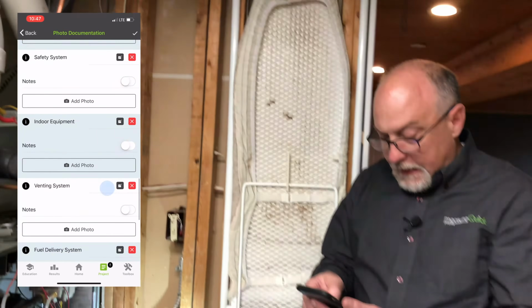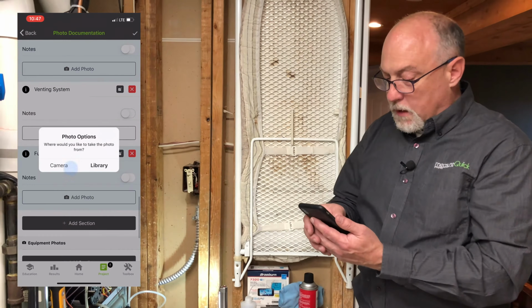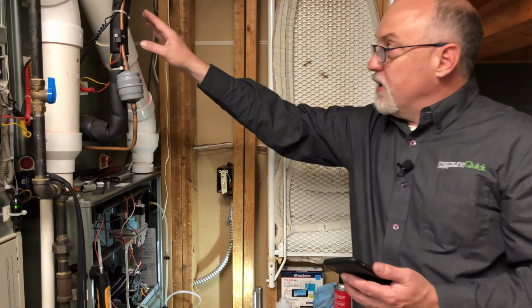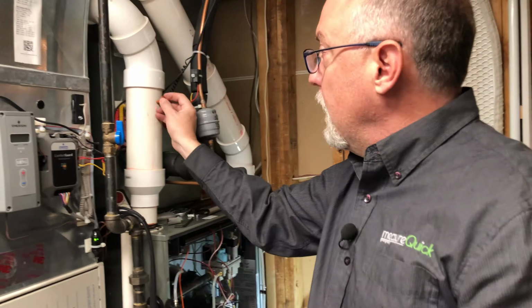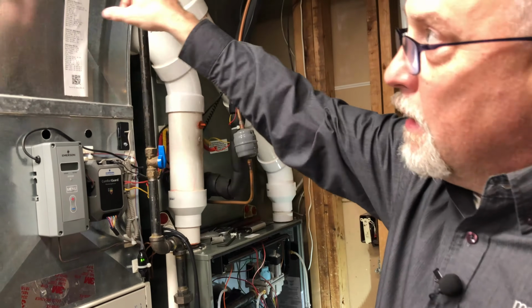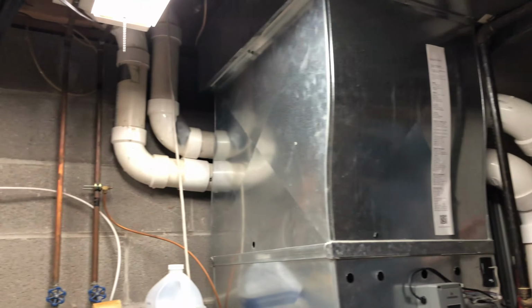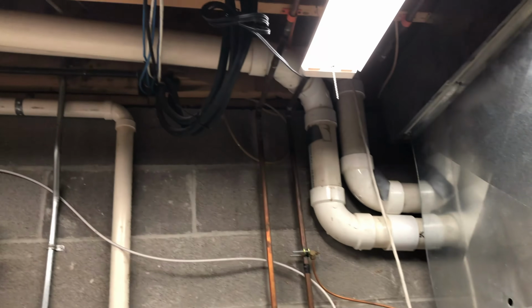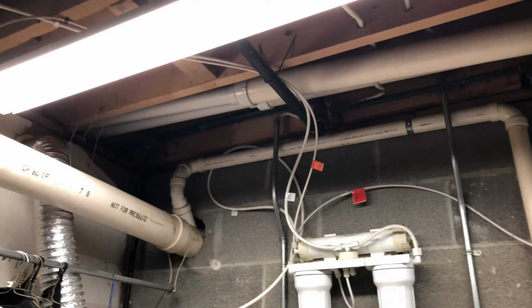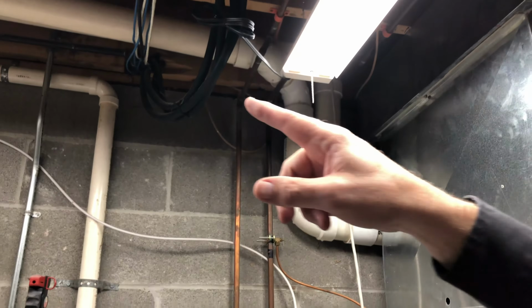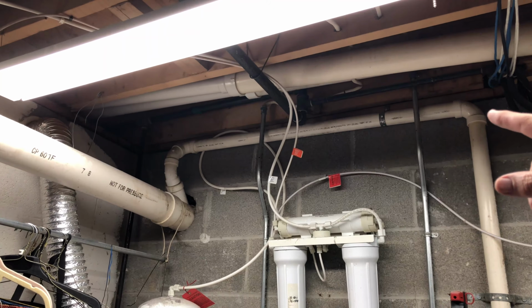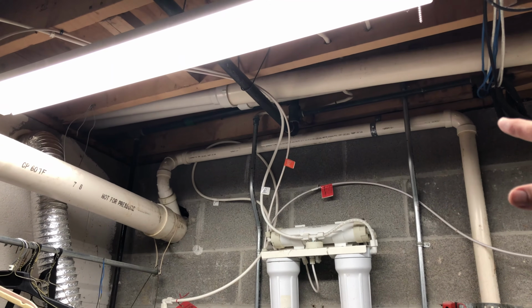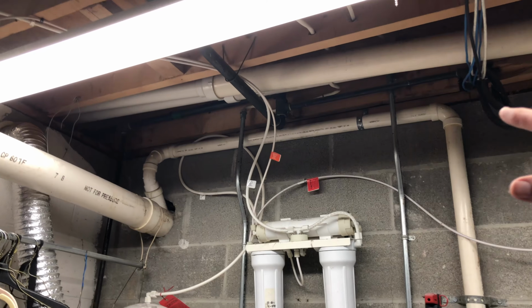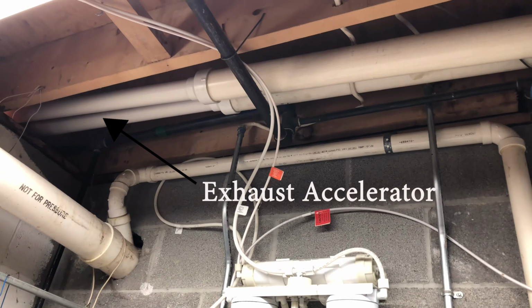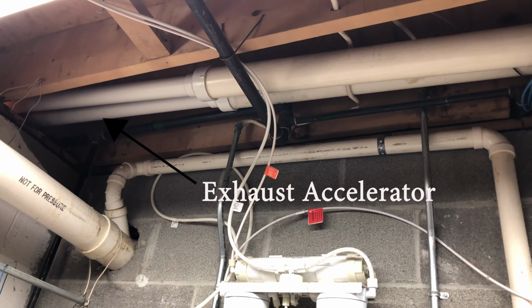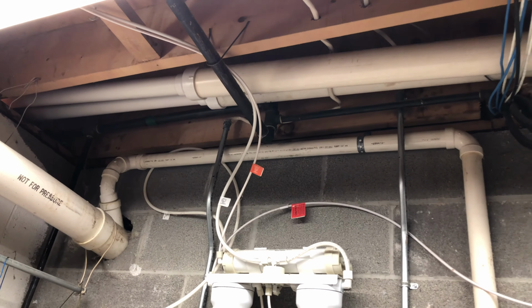Then any other equipment we want to take. Venting on these is probably one of the most important things. Look at your vent system. Make sure that the vent doesn't have excessive elbows. So I've got 1, 2, 3, 4, 5 elbows, and I'll consult my manufacturer's guide to make sure that vent is right. Down here at the end, at the top, this is called an exhaust accelerator, and if your appliance requires this, you need to make sure it is on there. That exhaust accelerator just necks down the pipe so that it speeds up the flue gases going out of the furnace to get them away from the house.